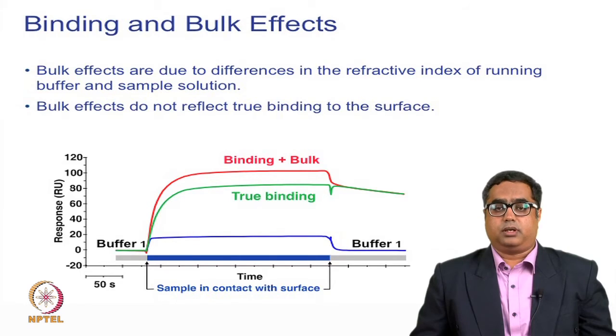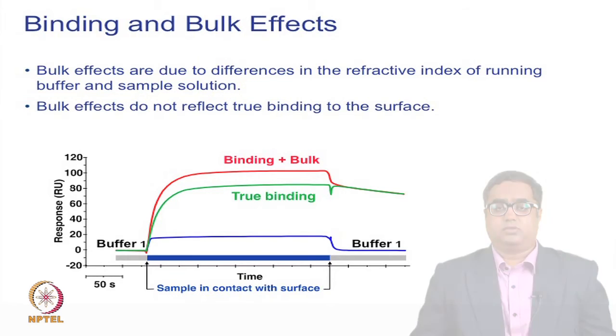Another important parameter is bulk — the difference in refractive index between the running buffer and the sample solution. This is where many assays go wrong and fail to yield proper kinetic data. It is recommended to equilibrate analytes to the running buffer to obtain good kinetic data.